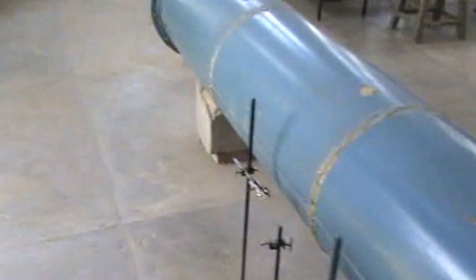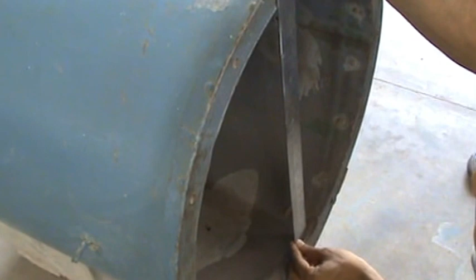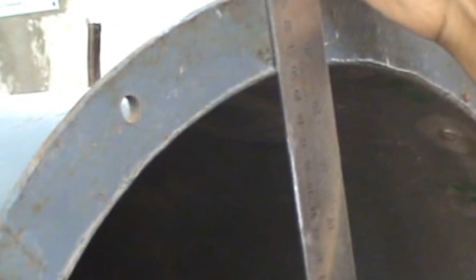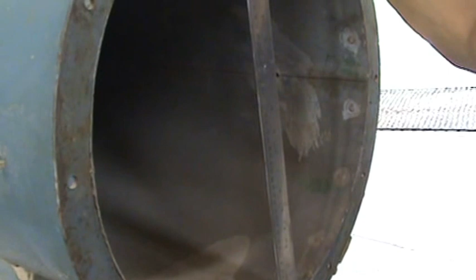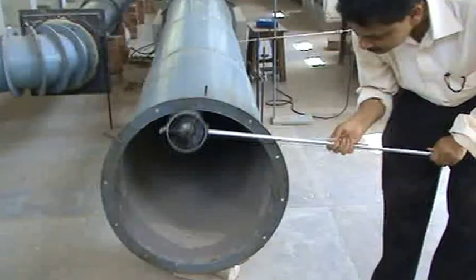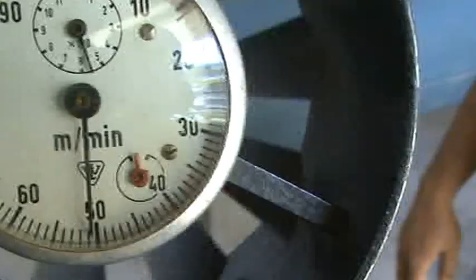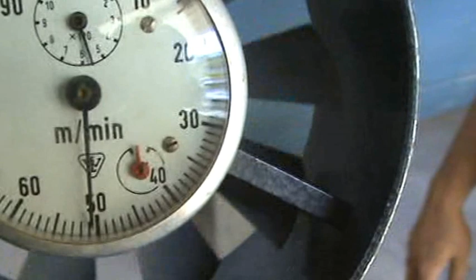Experiment now. First we will take the dimension of the duct, the diameter of the duct, to know the area of the duct, which is nothing but the outlet of the fan and also the area of the inlet of the diffuser. So the diameter of this duct is found to be 50.2 centimeter. Got at 50 meter per minute.